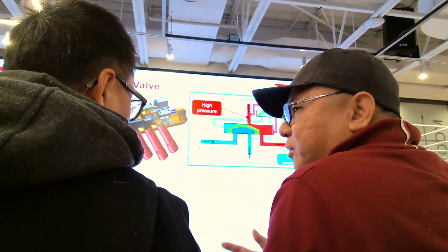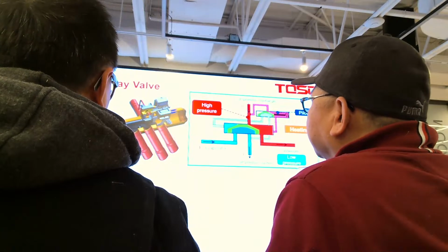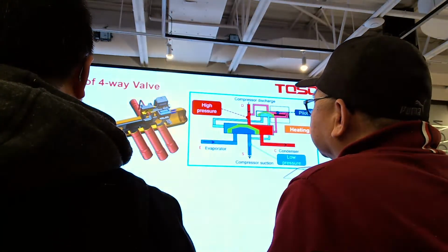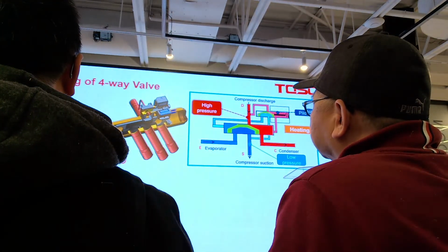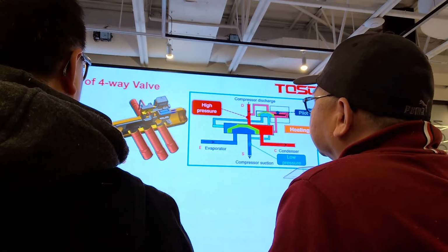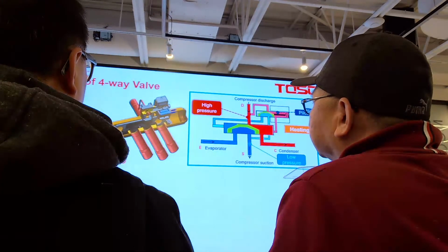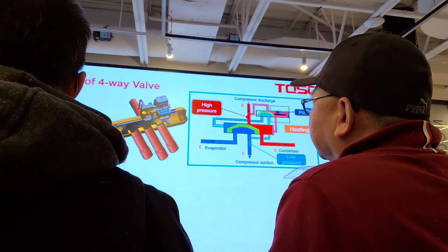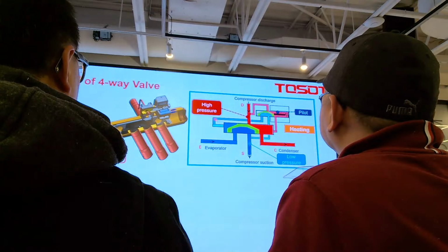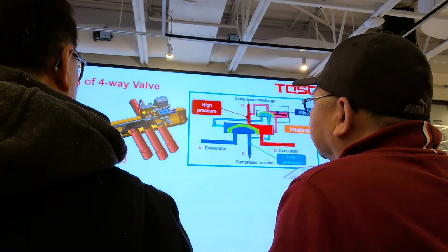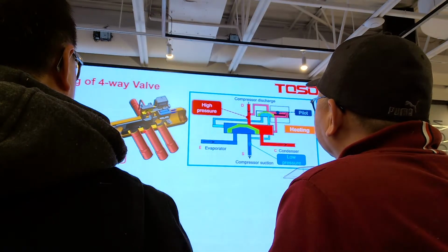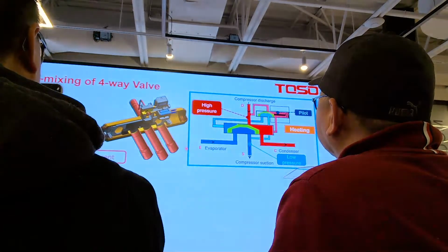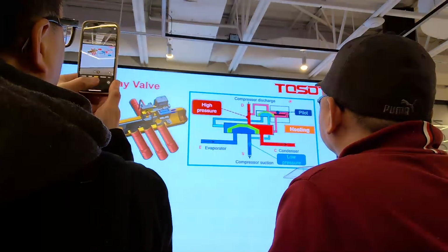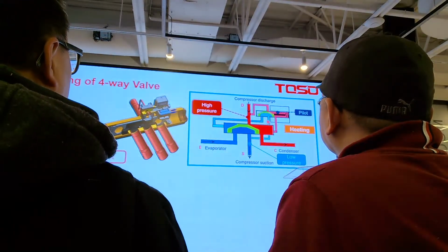And the next is for the four-way valve malfunction. For this one, it's not that common, but if it happens, there's no error code because the system will not judge this one, but the customer will complain it's no heating and no cooling. The reason is this one, because inside this four-way valve there is a slider. You just use this slider to change the direction, and I will display you a small animation how this four-way valve operates.